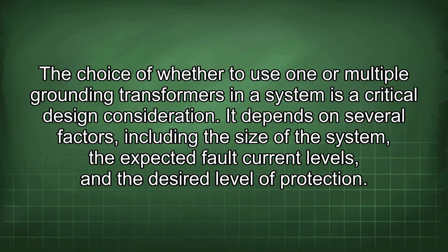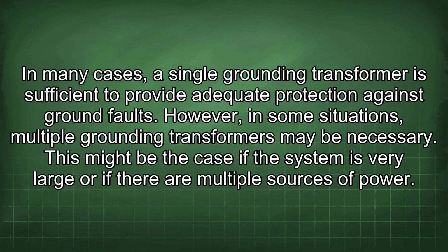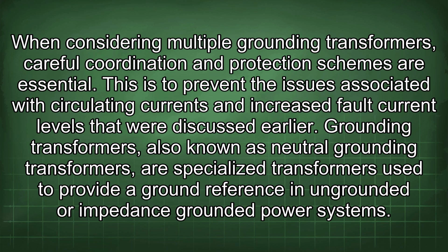damage. The choice of whether to use one or multiple grounding transformers in a system is a critical design consideration. It depends on several factors, including the size of the system, the expected fault current levels, and the desired level of protection. In many cases, a single grounding transformer is sufficient to provide adequate protection against ground faults. However, in some situations, multiple grounding transformers may be necessary. This might be the case if the system is very large or if there are multiple sources of power. When considering multiple grounding transformers, careful coordination and protection schemes are essential. This is to prevent the issues associated with circulating currents and increased fault current levels that were discussed earlier.